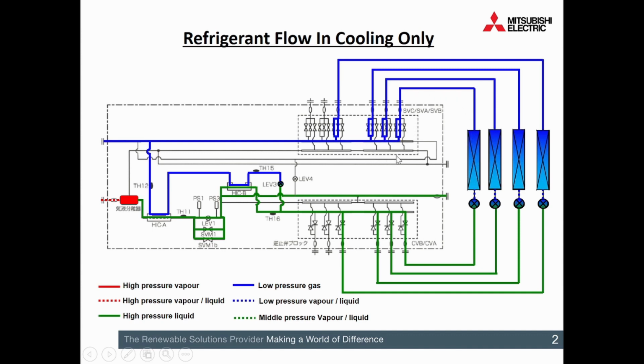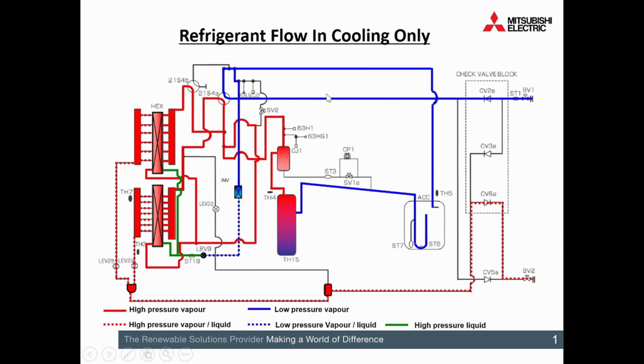It should have all become a vapor. Comes back into the actual outdoor unit, past my low pressure sensing. So again, that's what I'm aiming for, that 7.2 bar. Back round, and we dump it into that accumulator. So the accumulator is acting as a safety device to make sure I've only ever got vapor getting taken from the top of that accumulator and back to the compressor. It's also some way of storing the refrigerant, depending on how hard the system's working. And I'm also drawing oil out of the bottom of that accumulator as well. And we can look at TH5 and compare that to the low pressure sensing to get an idea of whether that refrigerant's actually all become a vapor as it's superheated.